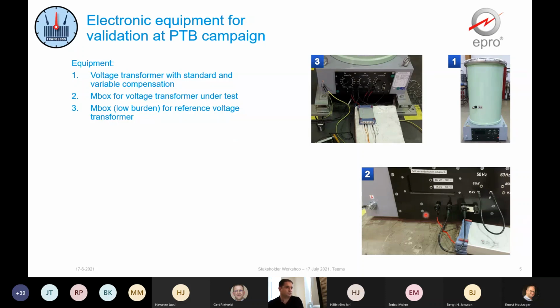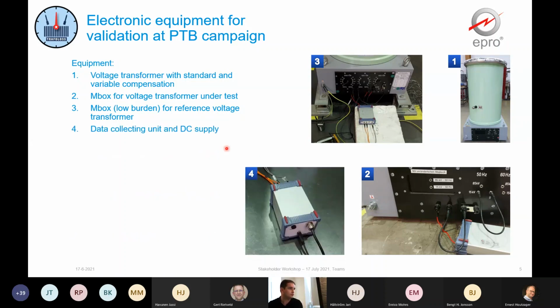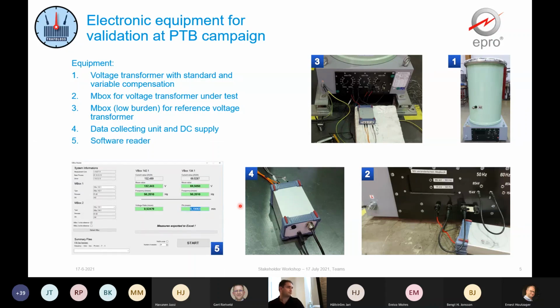Second box is for reference transformer. This is EPRO's reference transformer. The only difference between these boxes is this one has a lower burden. And the next unit was the data collecting and the supply for the boxes. This is where we prepare the data for the readout software. And finally, the software reader, where we can read out the values for two boxes and the phase displacement between them.